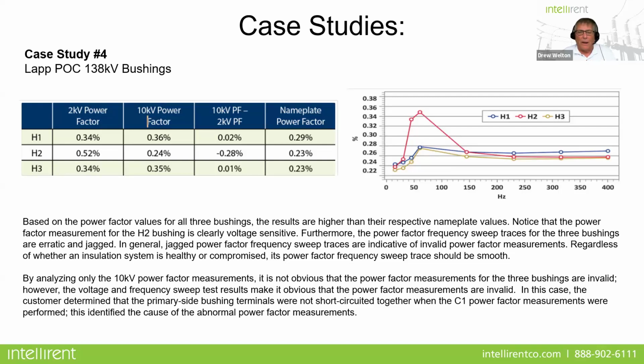Okay, now this one was totally out of whack. This is case study 4 on a Lapp 138 kV bushing. Based on the power factor values of all three bushings, the results are higher than their respective nameplates. Notice the power factor measurement on the H2 bushing is clearly voltage sensitive. Furthermore, the power factor frequency sweep traces for the three bushings are very erratic. In general, jagged power factor sweep traces are indicative of an invalid power factor measurement. Regardless of whether the insulation system is healthy or compromised, the frequency sweep should be smooth. It shouldn't have any kind of jagged trace like that.